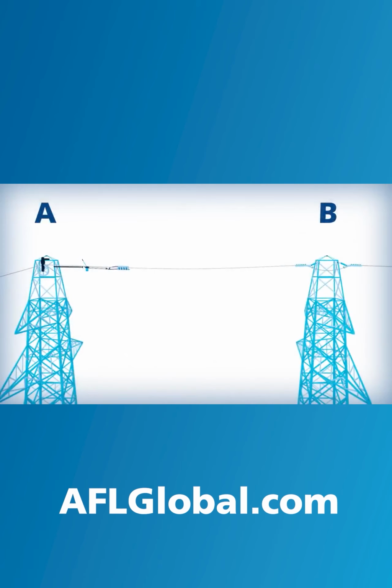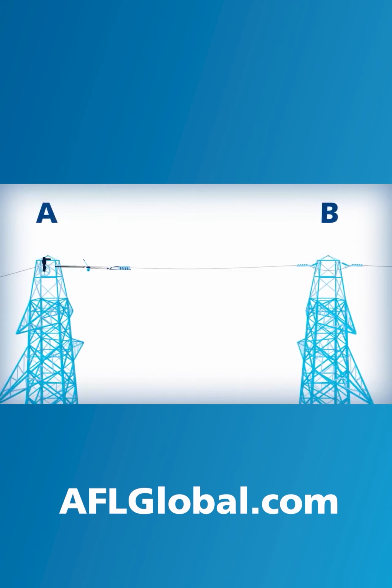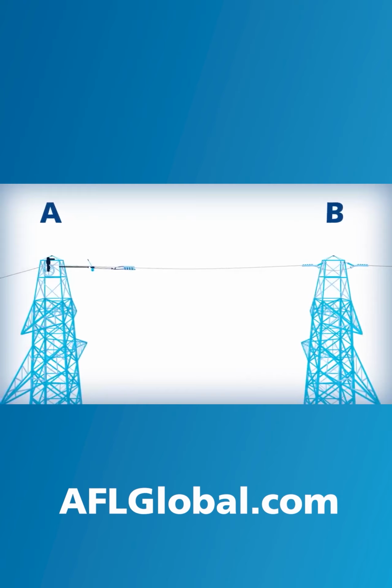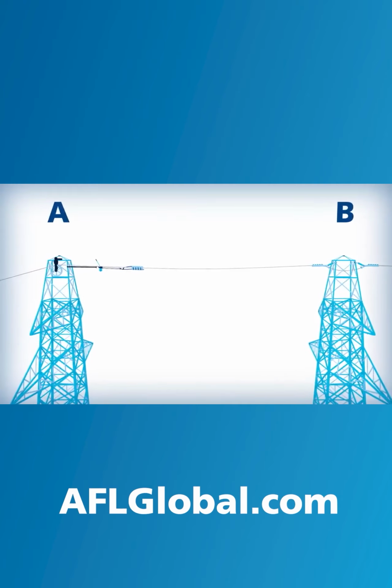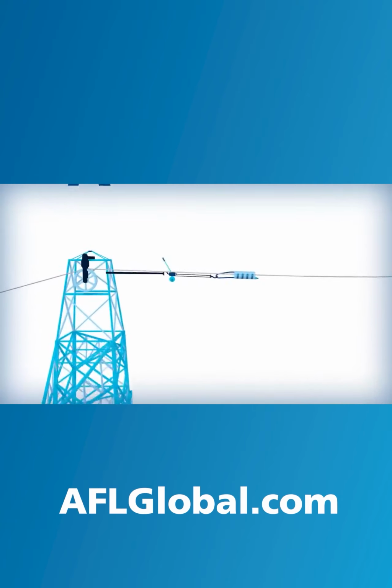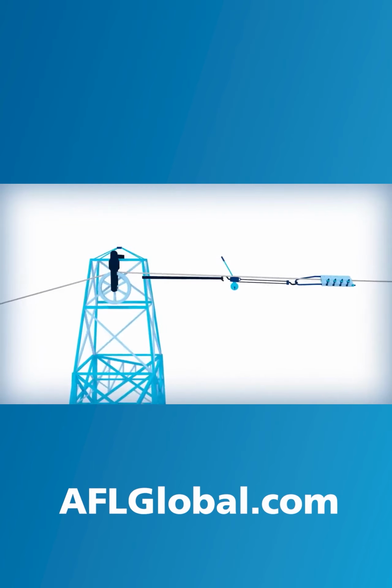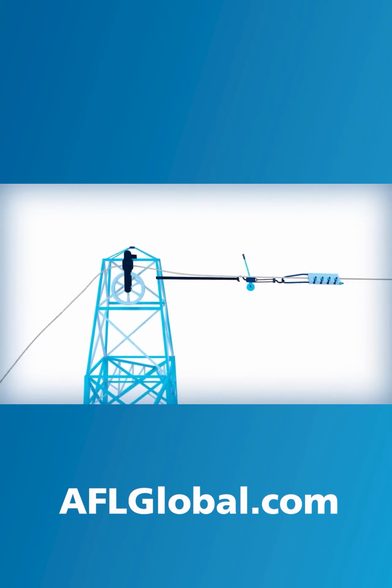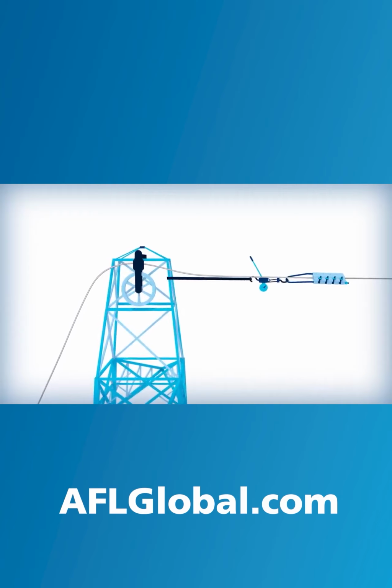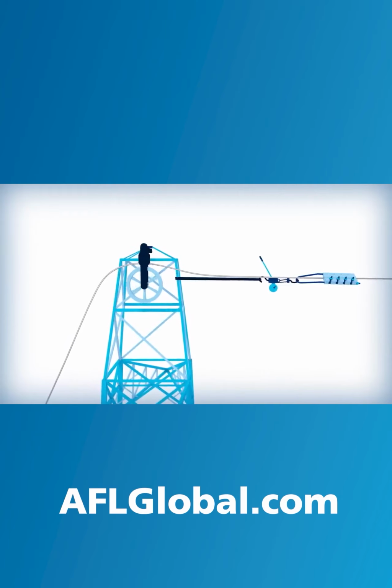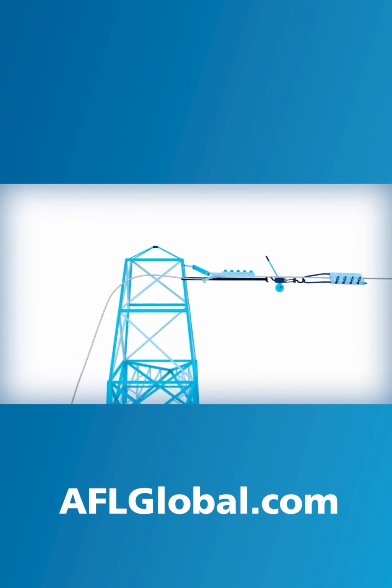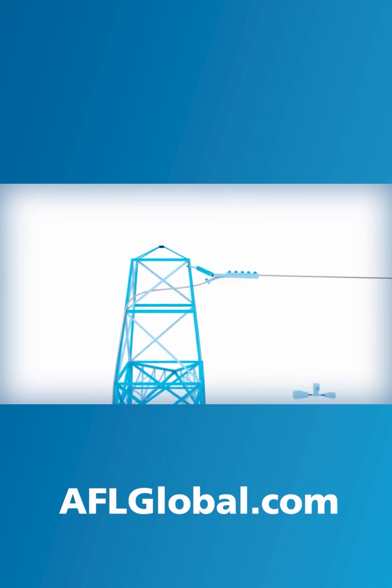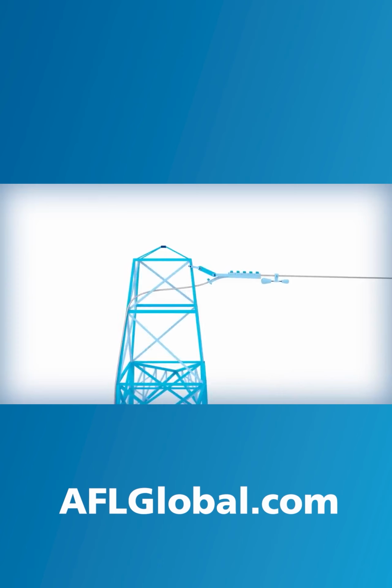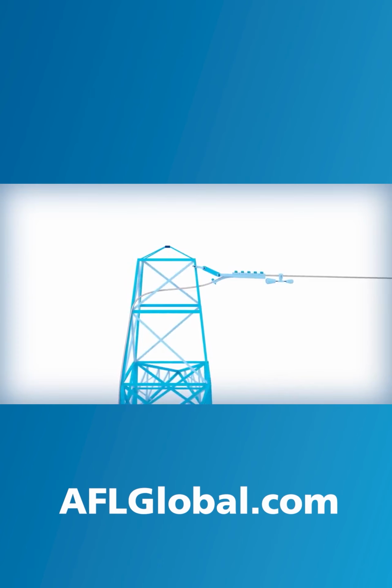To lift the OPGW from the stringing block, attach come-alongs to the cable on each side of the structure and place a hoist on the structure arm. The hooks of the hoist are placed on the come-along and jacked up to pull the OPGW out of the stringing block. The stringing block can then be removed and a dead end can be placed to attach the OPGW to the structure. If vibration dampers are required, they should be placed on the OPGW immediately after clipping in.